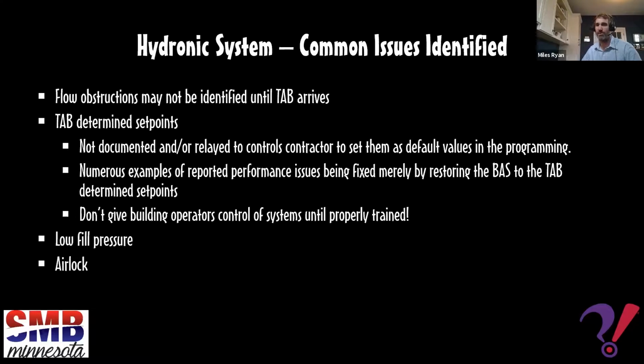All right, these next two things, low fill pressure and airlock, I'm going to turn over to Mark to talk a little bit about. Yeah, many times the control valves are closed during the flushing of the system. And when the flushing is complete, the valves are opened and air is bled out. If the system is not filled to take care of that air in the coils, then the pump experiences low inlet pressure, which affects the pump's ability to develop system pressure.